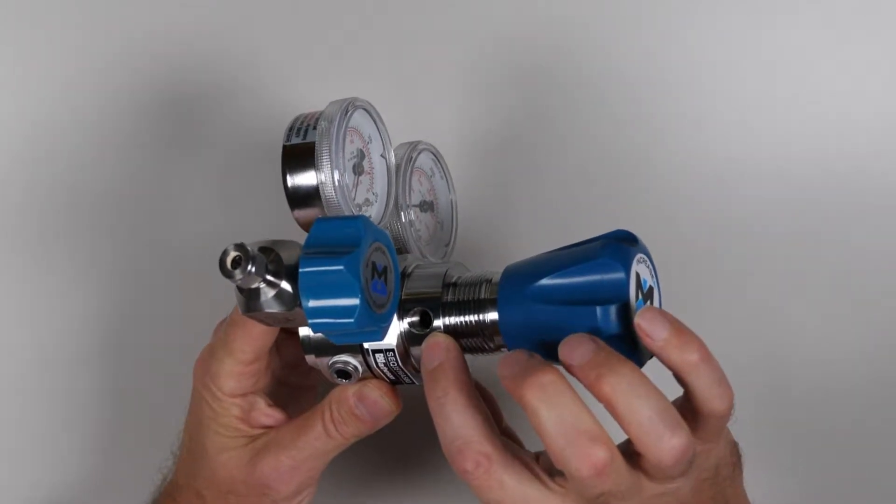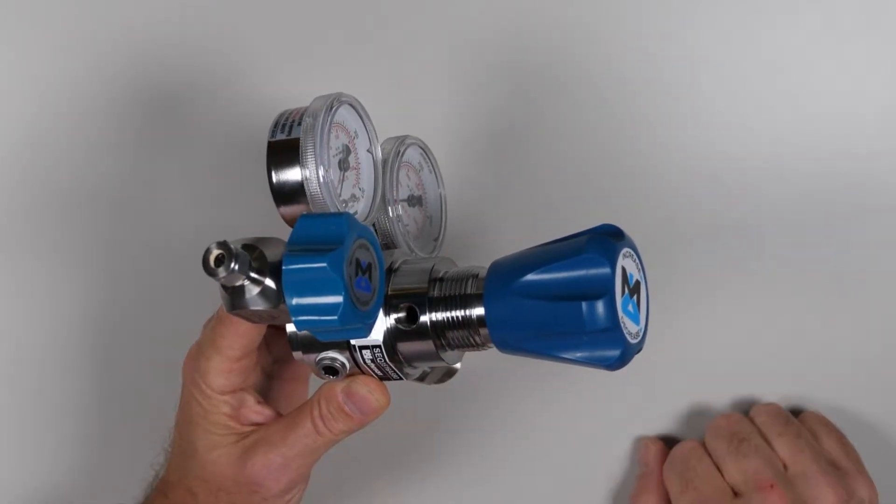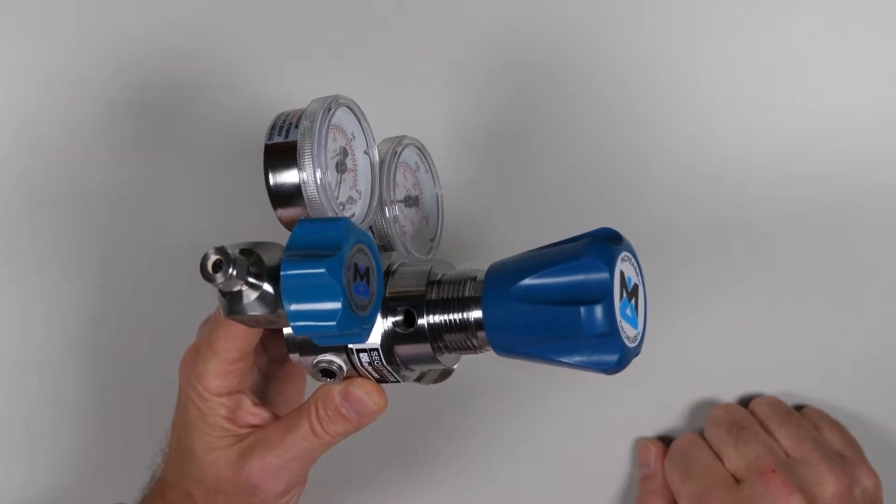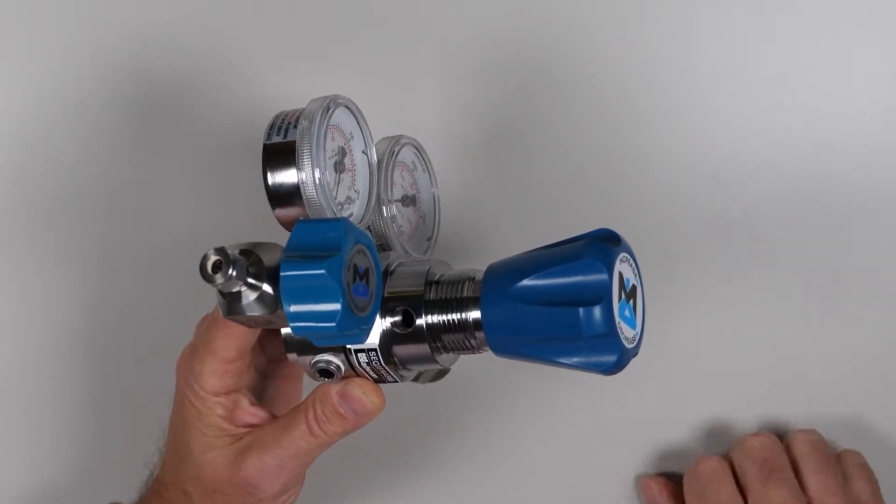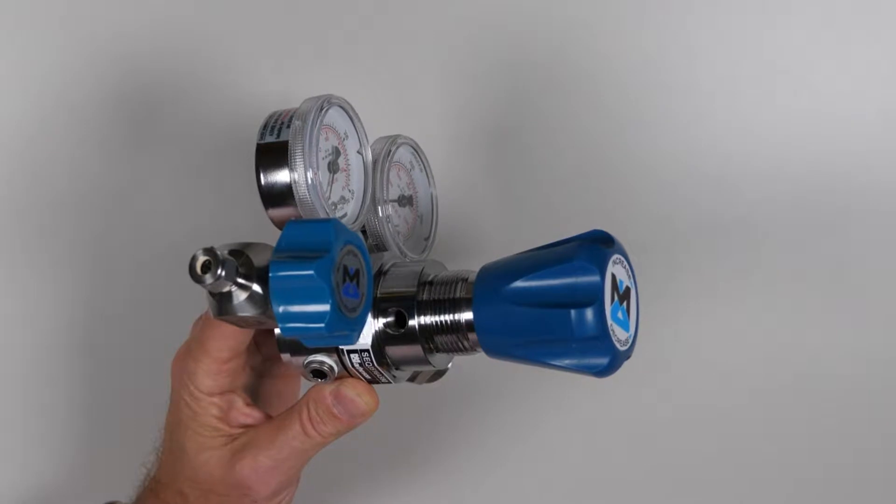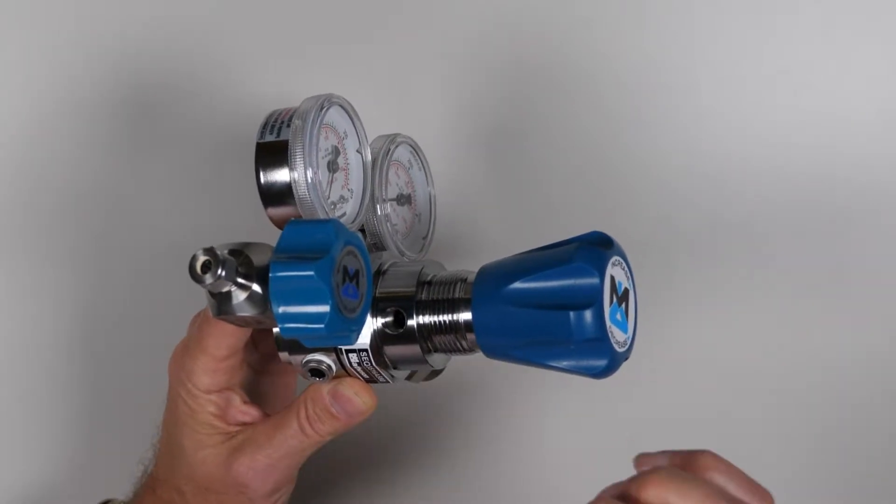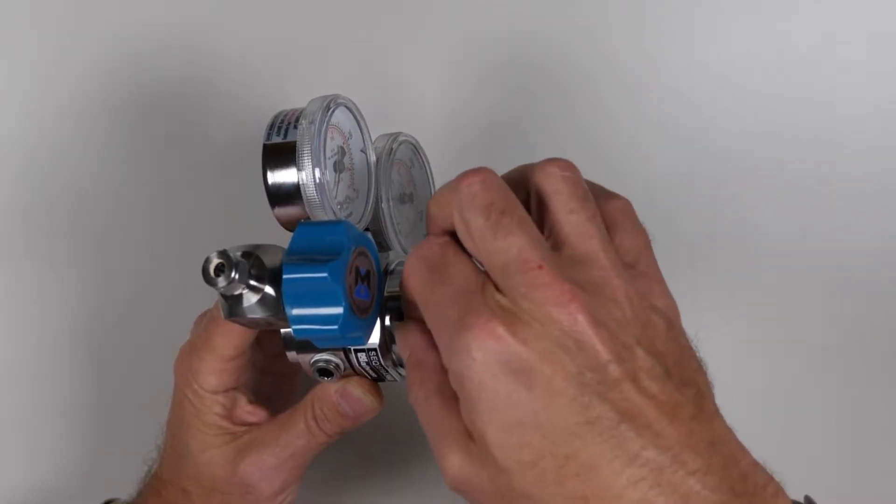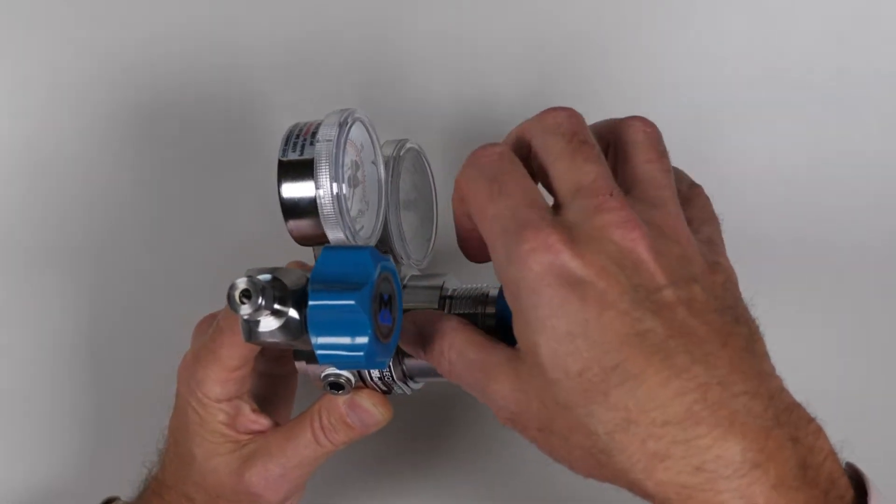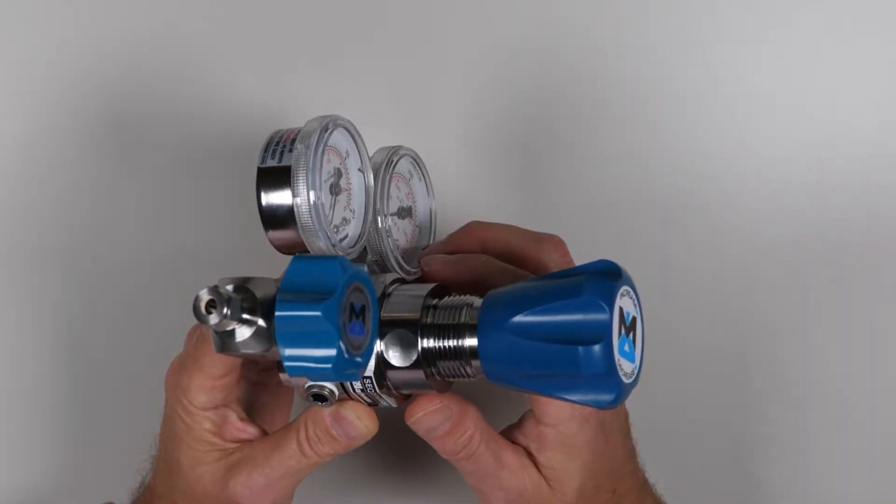The bonnet has a vent hole which is a safety feature that protects the bonnet from over pressurization if there's ever a leak past the diaphragm. The bonnet vent hole should never be plugged. Many of our pressure regulators have a sticker over the bonnet vent hole which will blow off easily should gas need to escape through the bonnet vent hole.